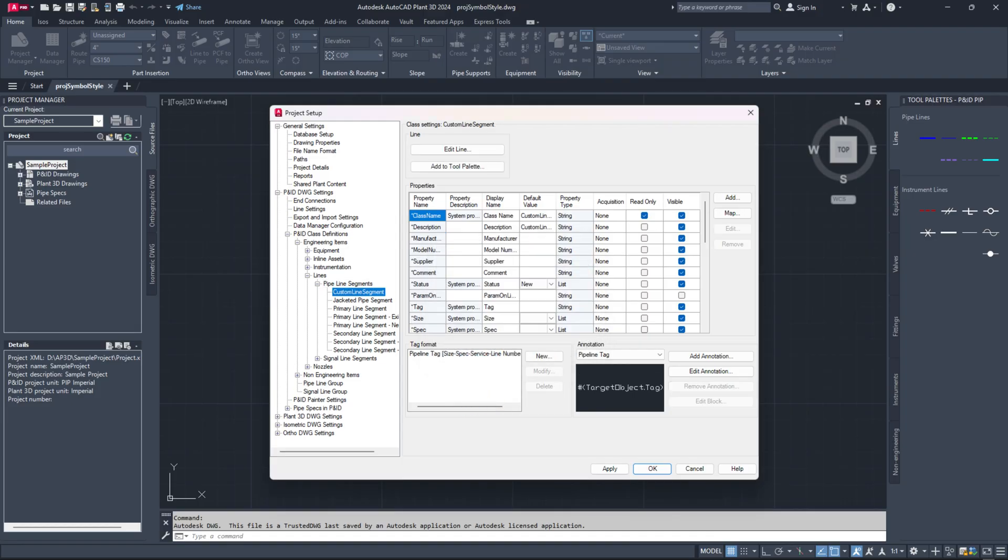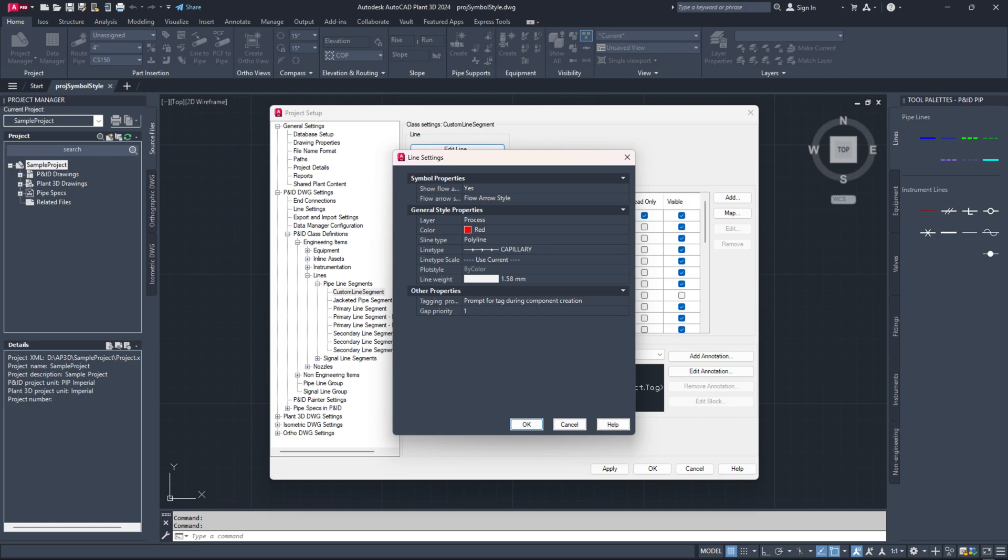After creating the class, click the edit line button. If you want to display process lines as a single line in the P and ID, set this line type to polyline and select the newly added line type from the drop down in the line settings dialog.